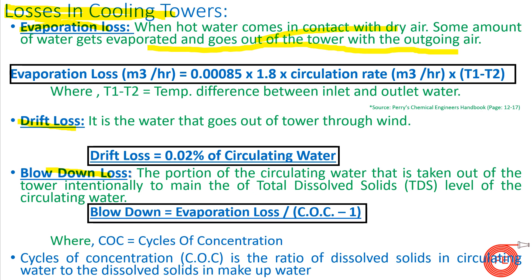Evaporation loss occurs when hot water comes in contact with dry air and some water gets evaporated and goes out with the outgoing air — you can see water going away above the fan of the cooling tower. This evaporation loss makes the system water-deficient. Evaporation loss is calculated as: 0.00085 × 1.8 × circulation rate × (T1 − T2), derived from the latent heat of vaporization formula.